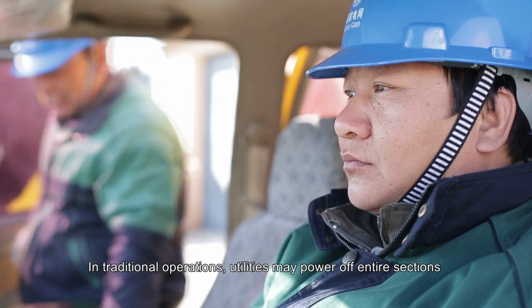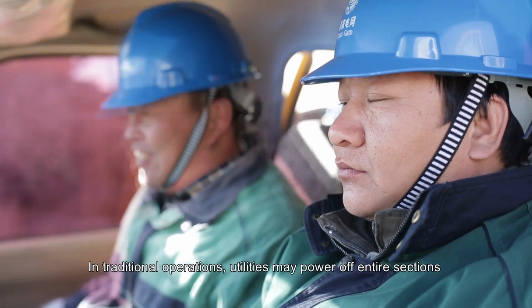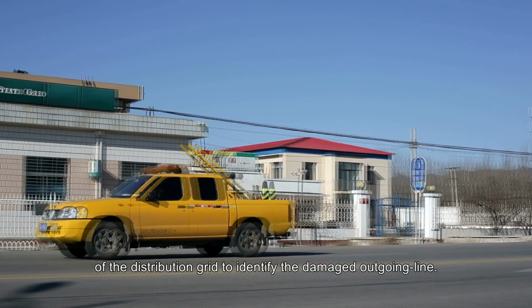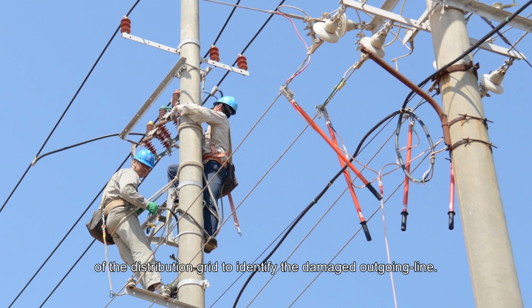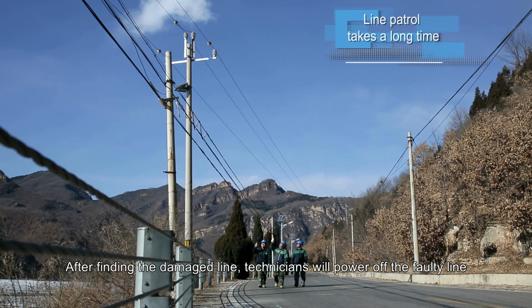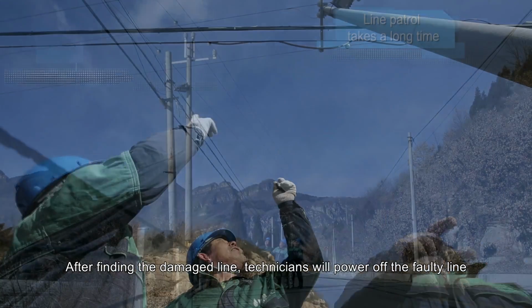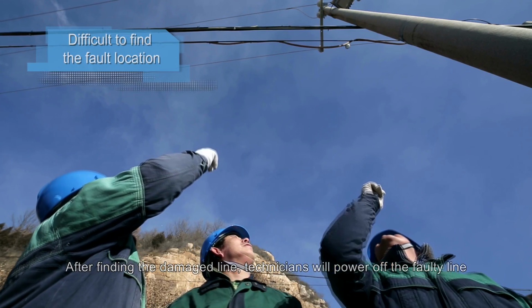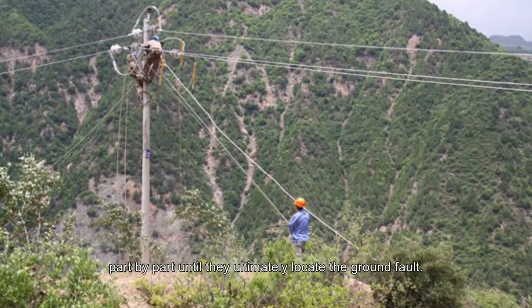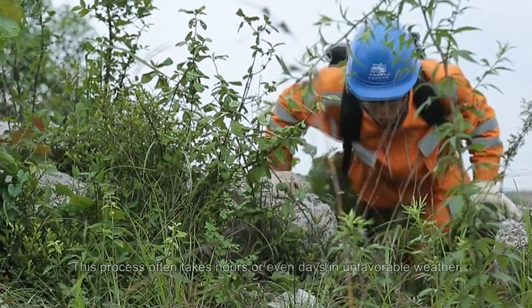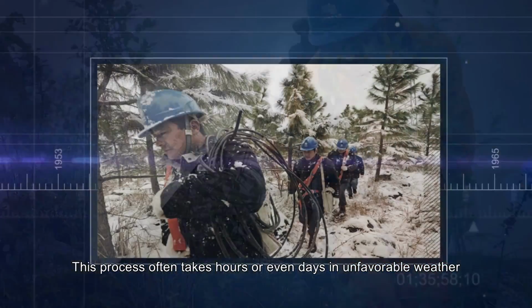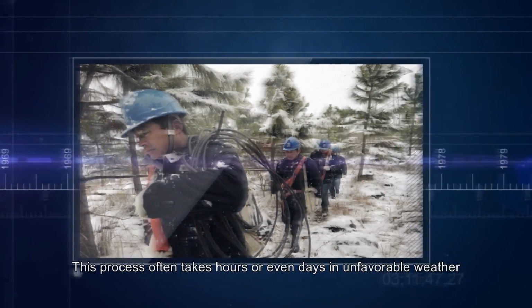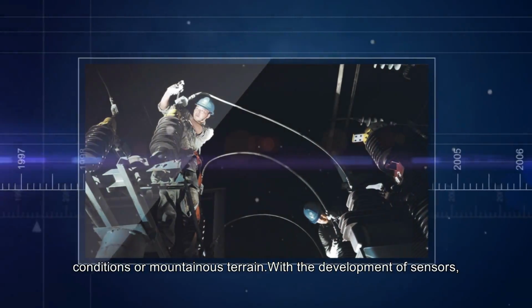In traditional operations, utilities may power off entire sections of the distribution grid to identify the damaged outgoing line. After finding the damaged line, technicians will power off the faulty line part by part until they ultimately locate the ground fault. This process often takes hours or even days in unfavorable weather conditions or mountainous terrain.